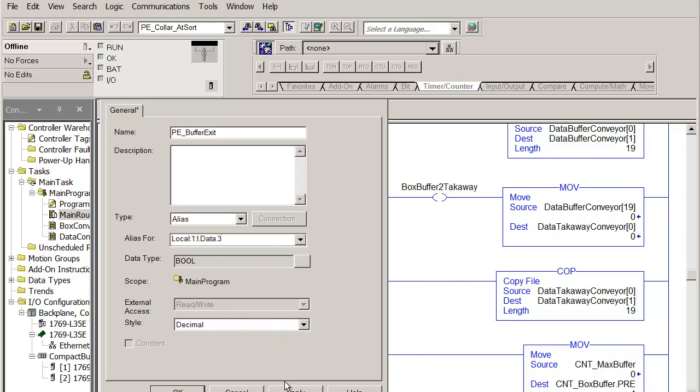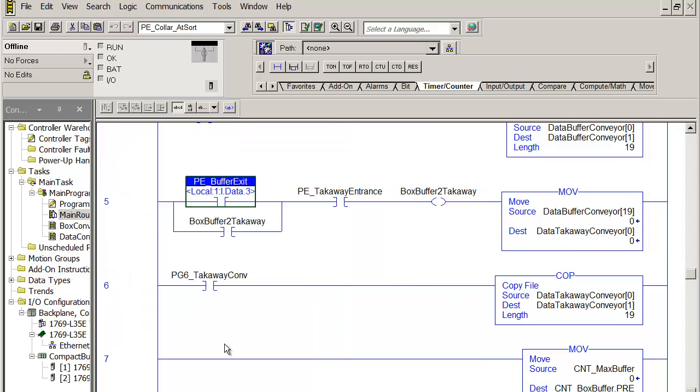That's what I have wired up. In other words, you'd be using electrical prints to alias. That's one thing that's really sweet about RSLogix 5000, ControlLogix, CompactLogix, etc., the Logix Engine. You can go through and write all of your code without knowing what your I/O addresses are, your I/O memory locations, and then later on go and alias them like we're just now doing.